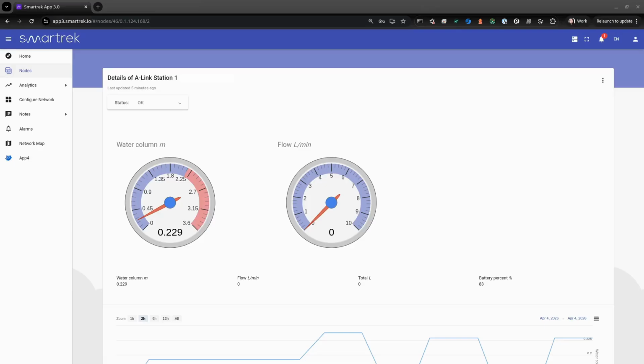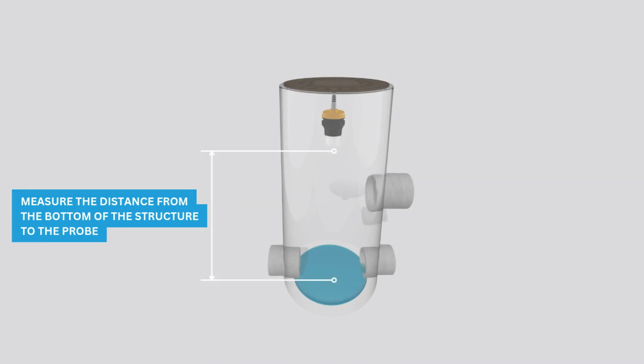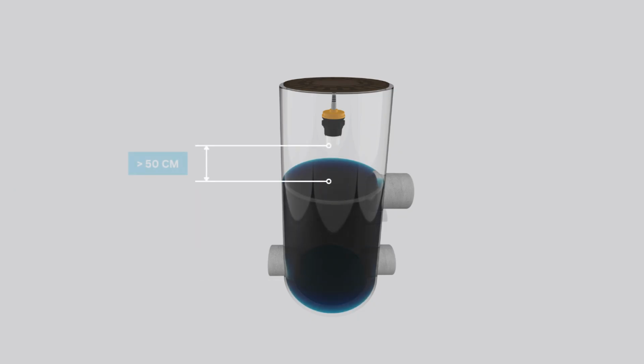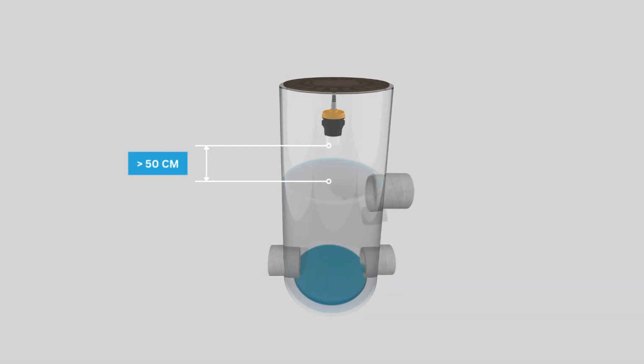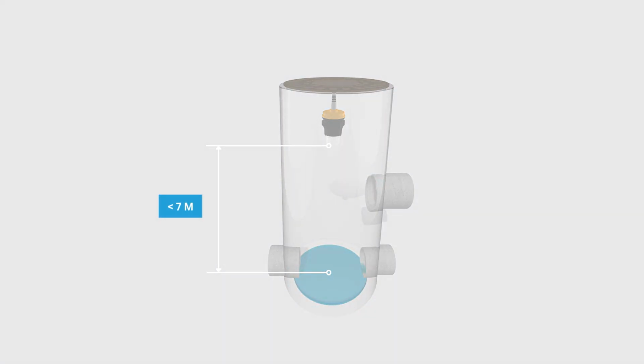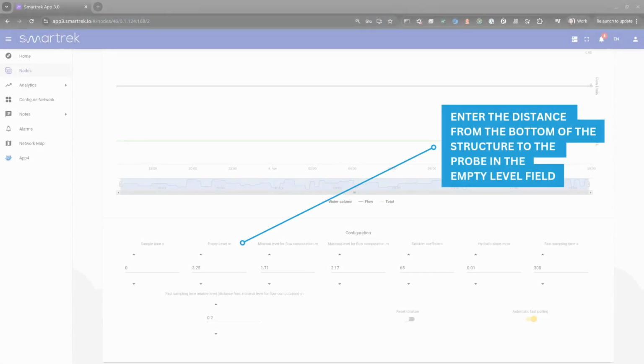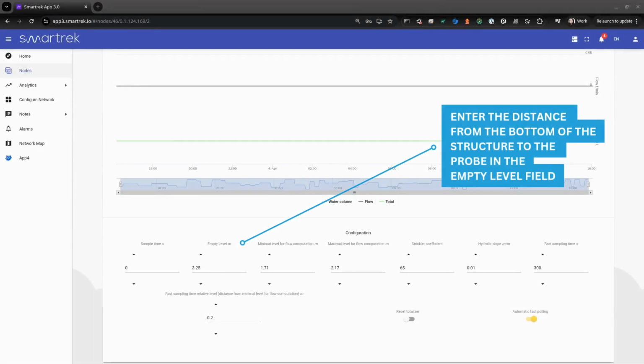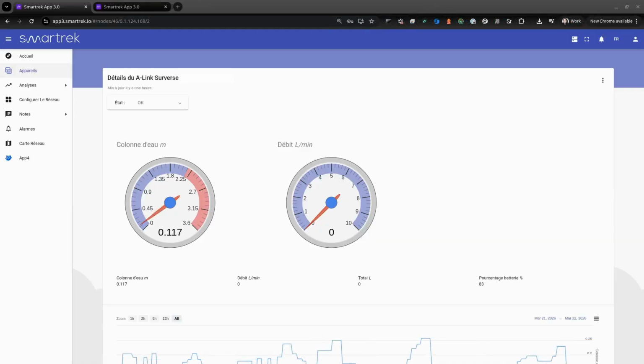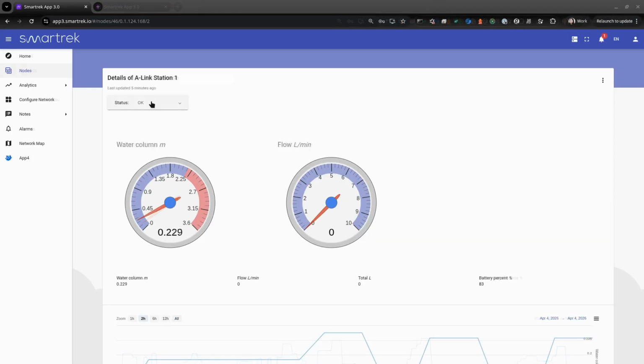Confirm that the probe is reading the correct water level. If it isn't, then measure the distance from the probe to the bottom of the structure. Make sure the probe is at least 50 centimeters from the highest water level, and no more than 7 meters from the bottom of the structure. Enter the measured distance from the probe to the bottom of the structure in the empty level field. Then click OK. Confirm that the probe is now reading the correct level.